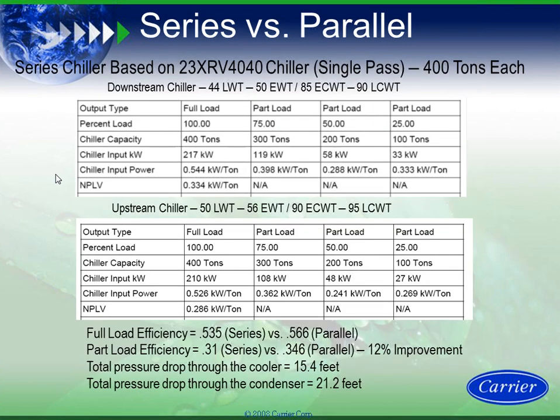My upstream machine went to 0.526, and my part load was at 0.286. Okay, full load efficiency 0.535 series, 0.566 parallel. Part load 0.31 series, 0.346 parallel. 12% improvement. My total pressure drop on the cooler on the series is 15.4.